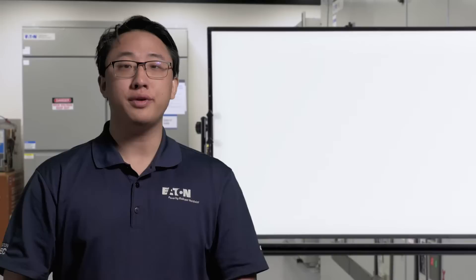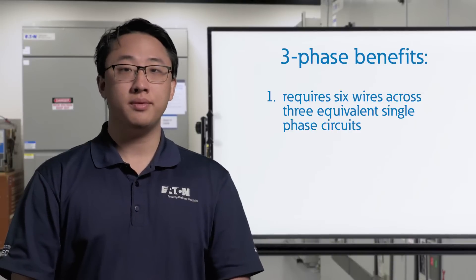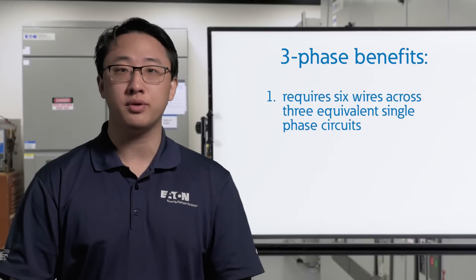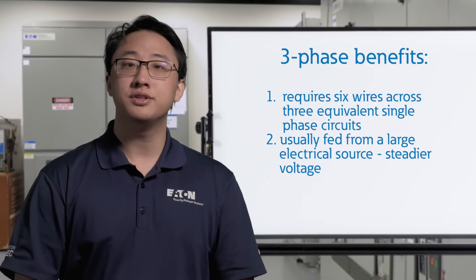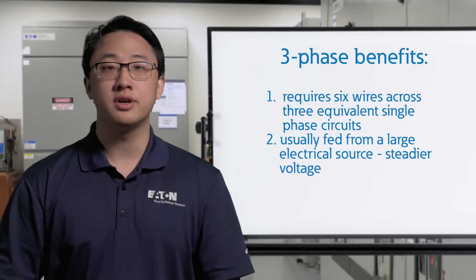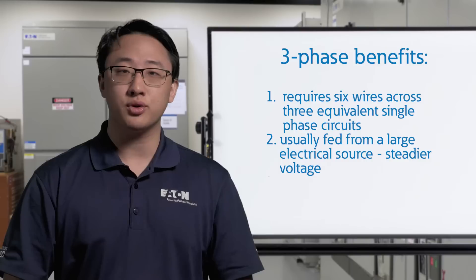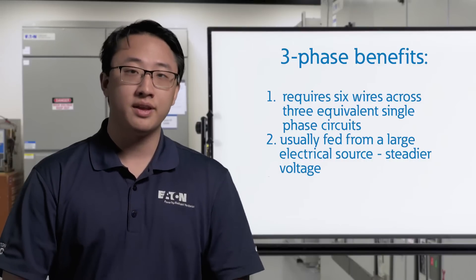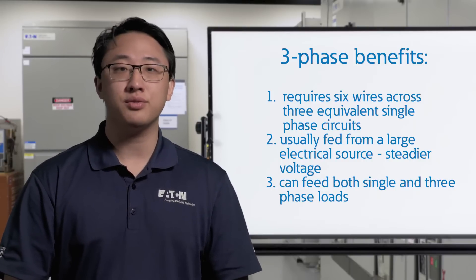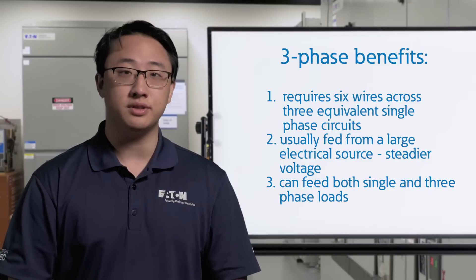In general, three-phase power has three main benefits over single-phase power. One, the power transmitted with three wires in a three-phase system would require six wires across three equivalent single-phase circuits. Two, three-phase power is usually fed from a larger electrical source, which provides much steadier voltage. This is required by many heavier commercial loads, such as motors. And three, three-phase systems can feed both single and three-phase loads, while single-phase systems are designed to only feed single-phase loads.